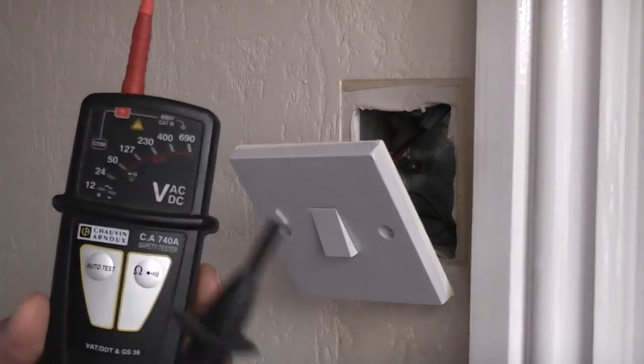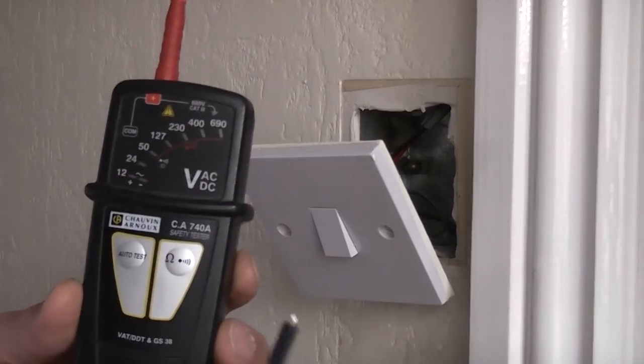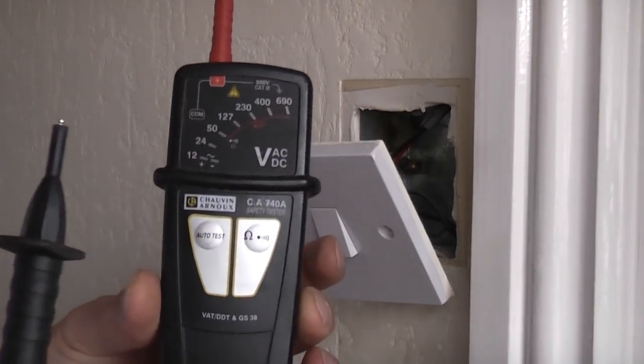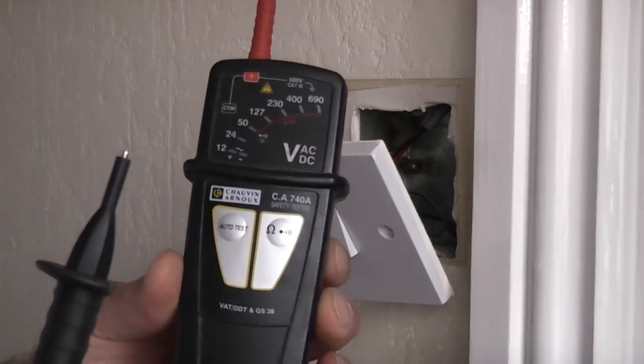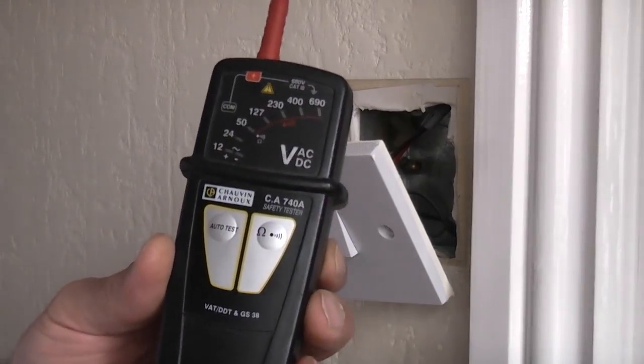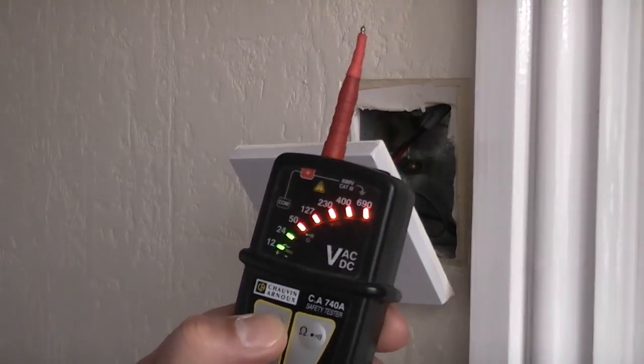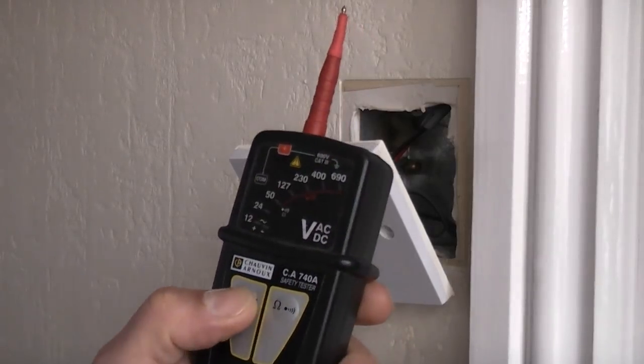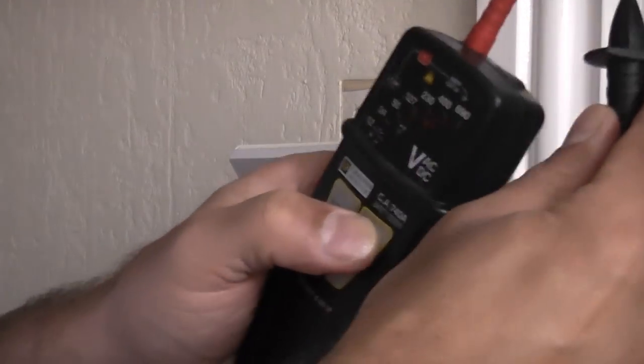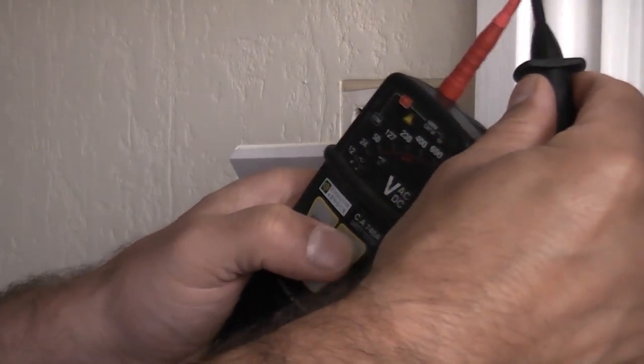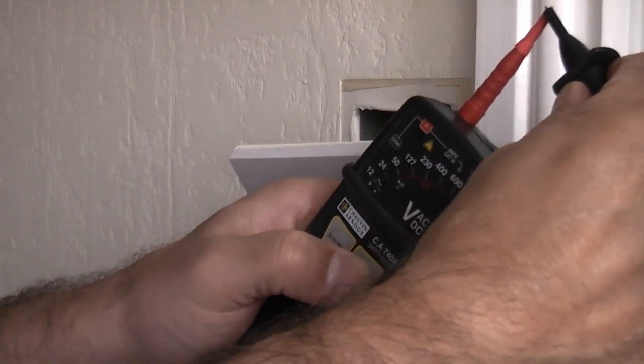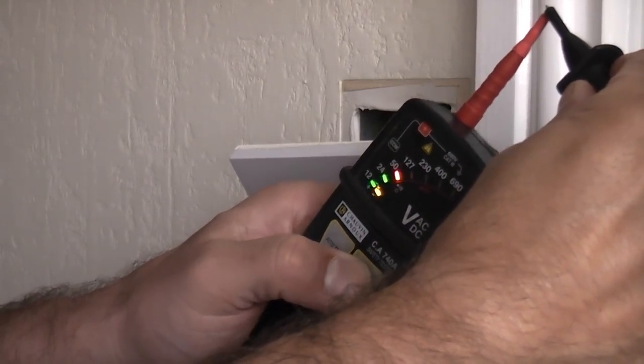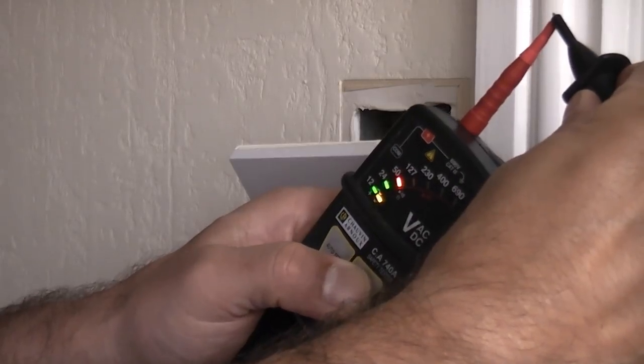Before we touch any of the wires at the back we need to ensure that they are completely dead. We're going to do that using this GS38 approved voltage tester. This one has a self test function so we're going to press the auto test. You can see that that is working. We're then going to check that the leads are working by measuring the resistance. I'm going to touch both probes together and then press the ohms button so you can see that the leads are working.